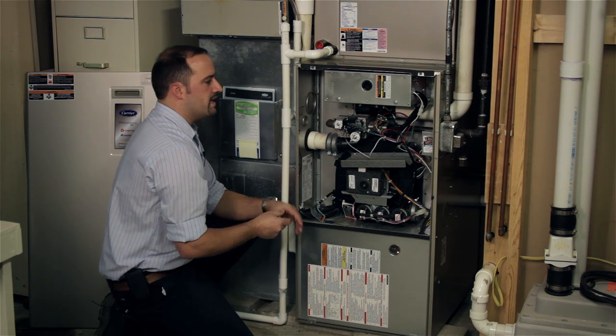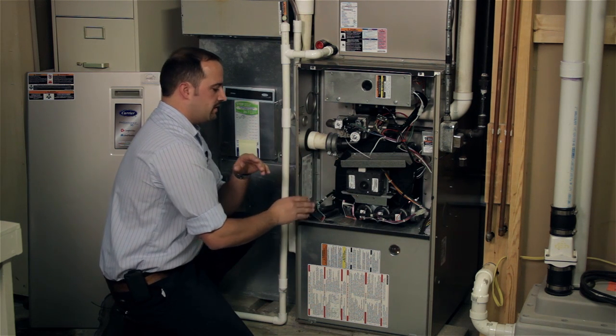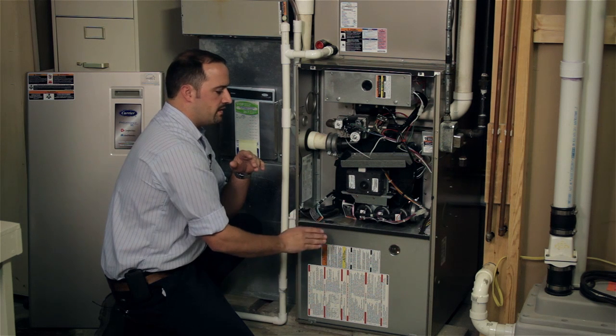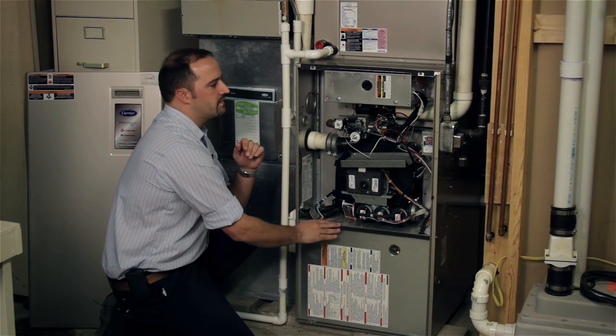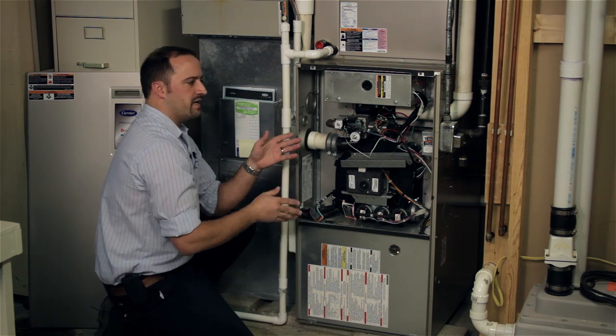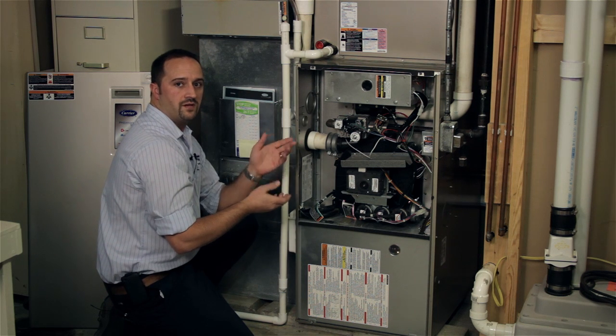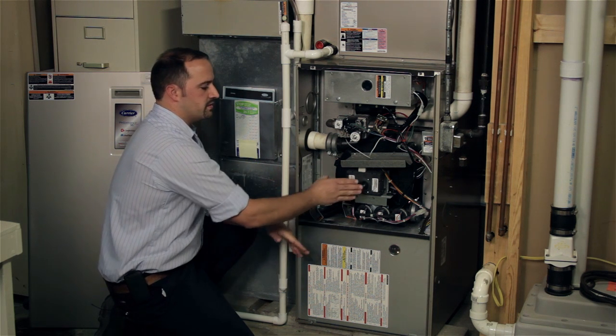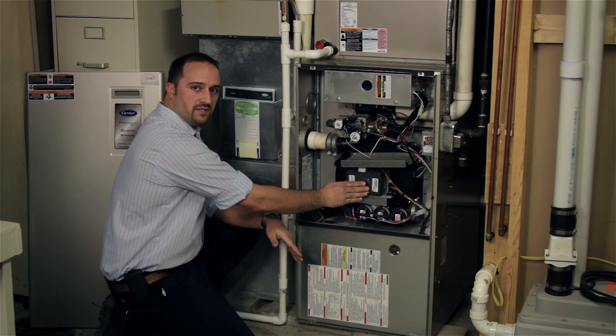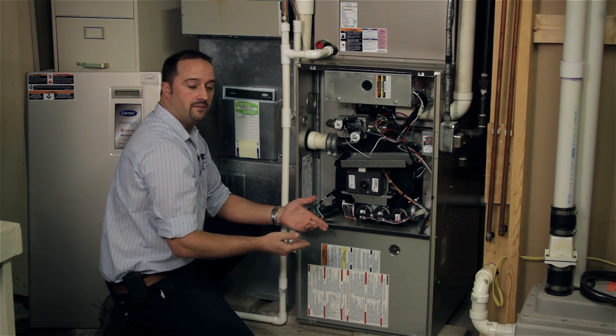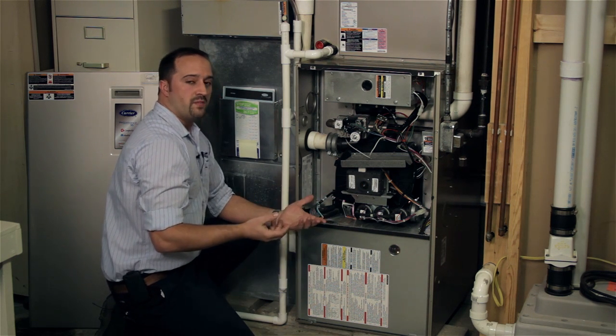After that, he's going to go ahead and make sure everything's nice and clean. He'll clean out any of the drains. He'll check all the wires, make sure they're nice and tight. He'll go ahead and put the furnace back together, and then he'll go ahead and fire it off and start testing it from there. He's going to ensure that the motors are running the proper direction. He's going to ensure that the bearings are fine. He's going to ensure that they're pulling the right amount of power.